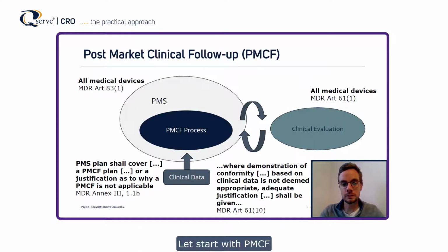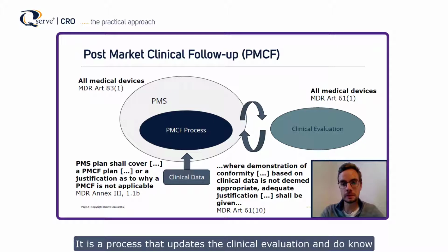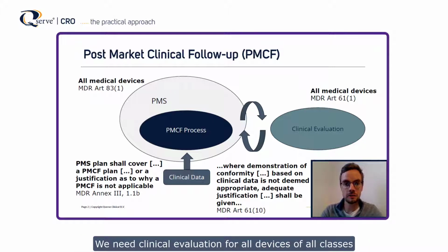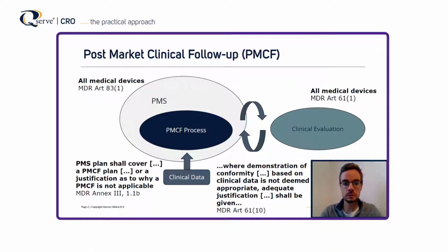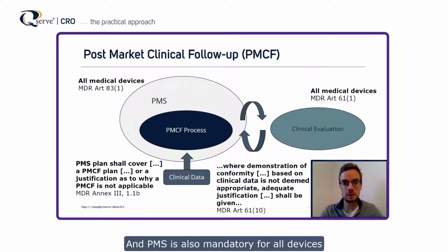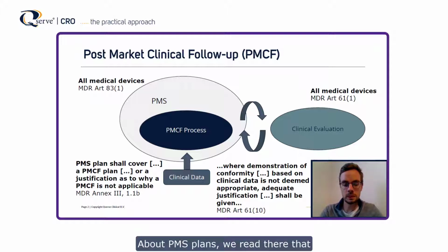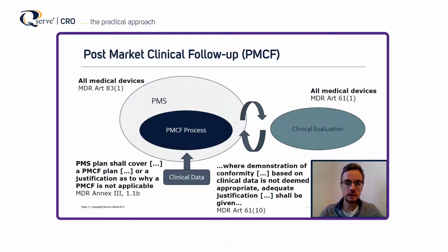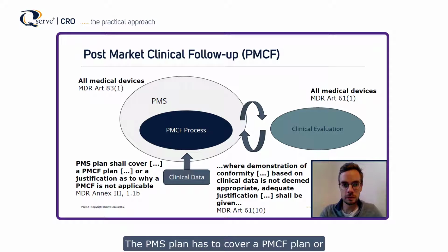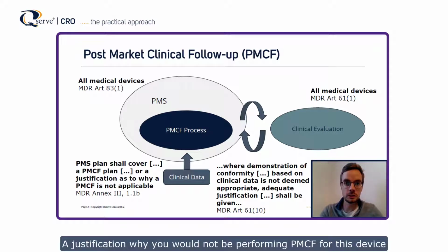Let's start with PMCF. It's a process that updates the clinical evaluation. And you know we need clinical evaluation for all devices of all classes. PMCF is part of PMS, and PMS is also mandatory for all devices. But when we look at the text about PMS plans, we read there that the PMS plan has to cover a PMCF plan or a justification why you would not be performing PMCF for this device.